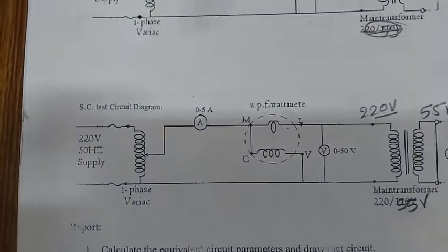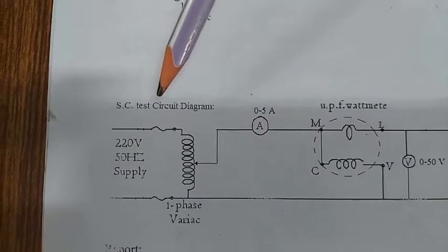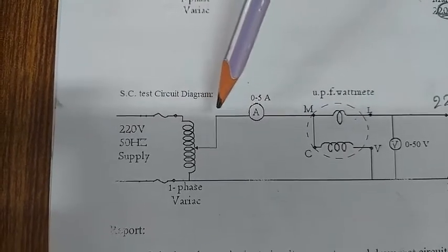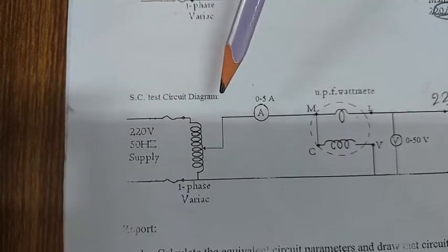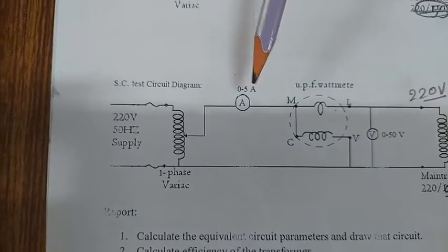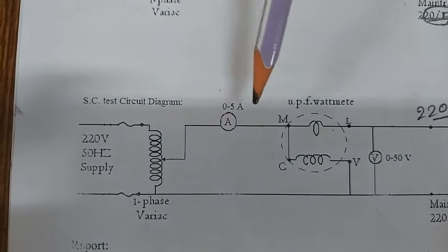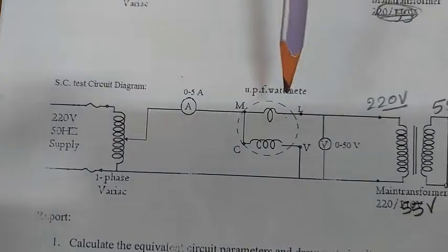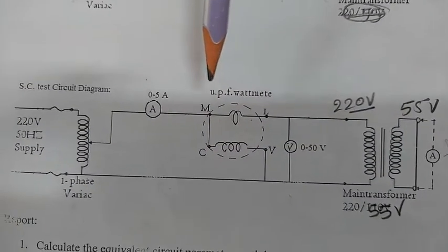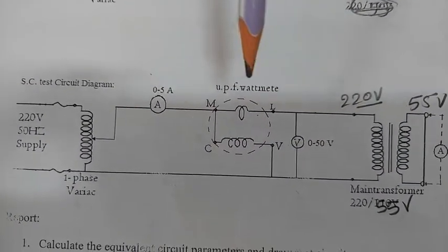First of all, the 220 volt variac will be there, so we will get a maximum of 220 volt, or we can even go higher depending on the manufacturer specifications. After that, we will use one ammeter to read the input current which will be consumed by the primary winding, that is the 220 volt side winding. And after that, the wattmeter will be connected.